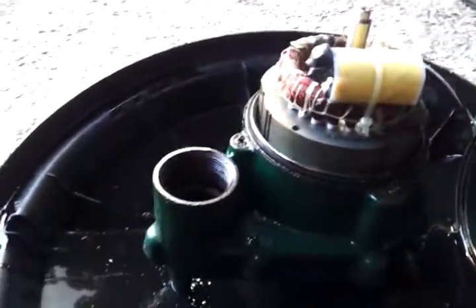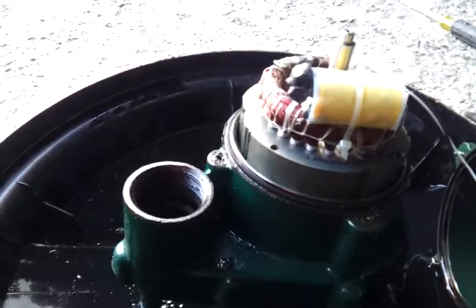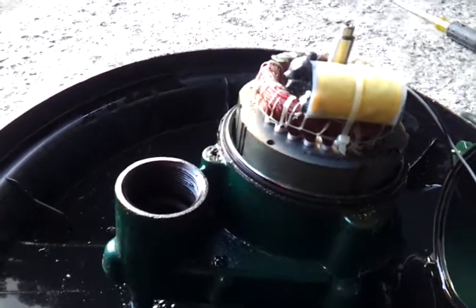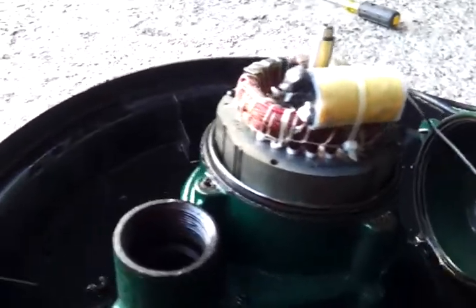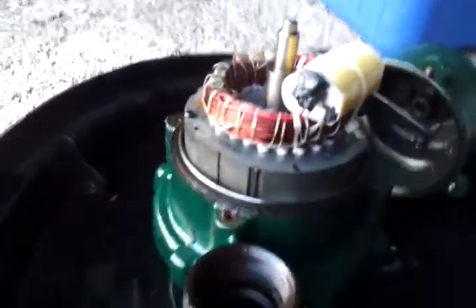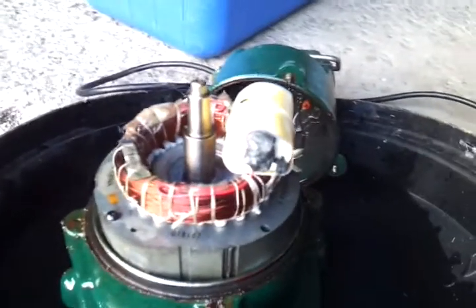This Zoeller pump actually failed after less than about three years of service. The reason I've got this one out now and I'm checking into it is because the exact same replacement pump that we put in 25 months ago has now failed as well.